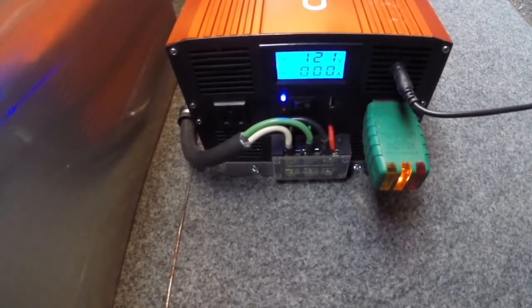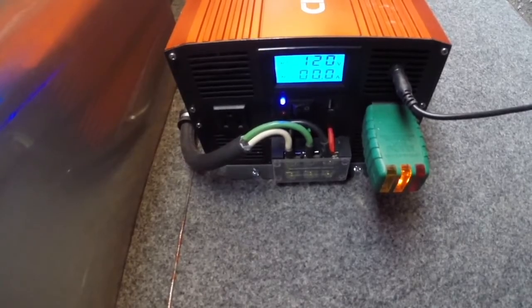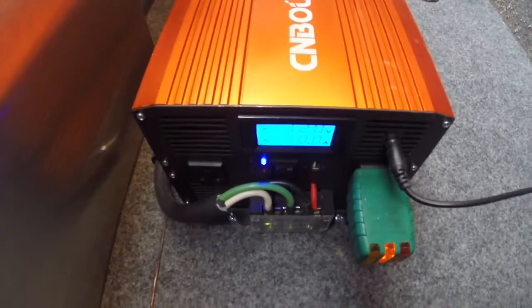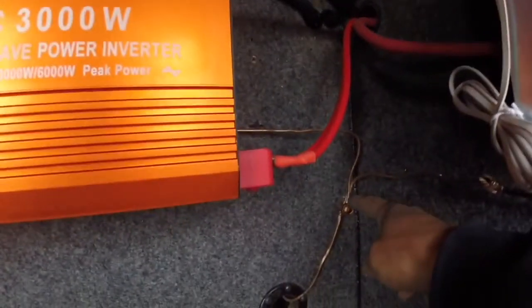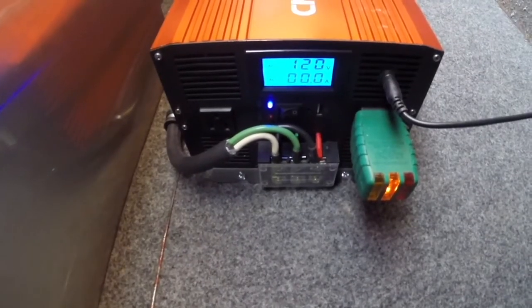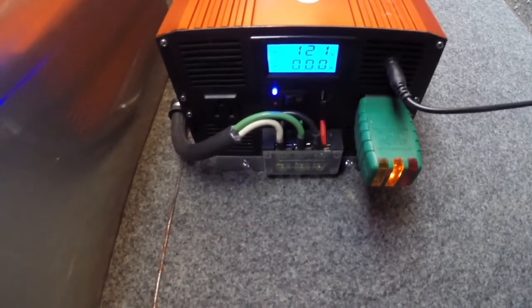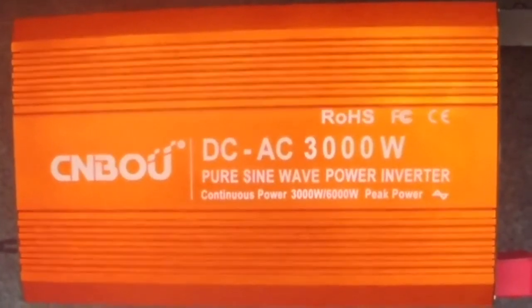When you're running an inverter, it does not have a grounding field, so it will always show an open ground — this is perfectly normal. The important thing with an inverter is that it's grounded to the frame. I have that ground coming from the frame grounded to the outside of the inverter. Also, the green wire — the ground on the direct connect — is wired into my ground bar on my transfer box.